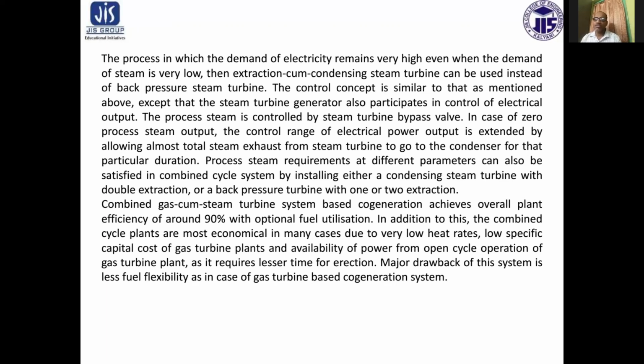In addition to this, combined cycle plants are most economical in many cases due to very low heat rates, low specific capital cost of the gas turbine plant, and availability of power from open cycle operation of the gas turbine plant, as it requires lesser time for erection. The major drawback of this system is less fuel flexibility, as in the case of gas turbine based cogeneration system.